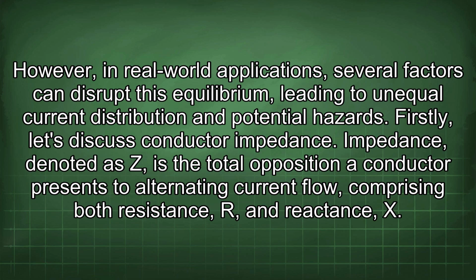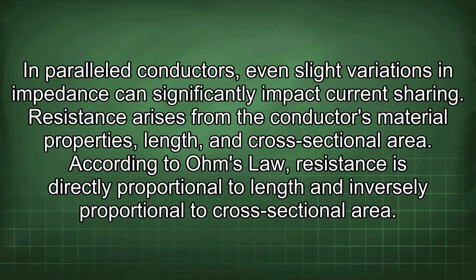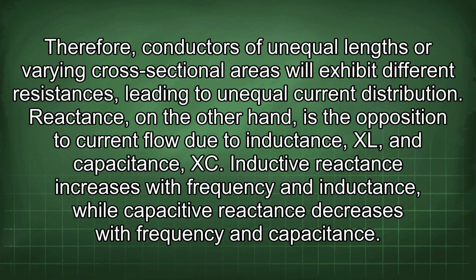Firstly, let's discuss conductor impedance. Impedance, denoted as Z, is the total opposition a conductor presents to alternating current flow, comprising both resistance R and reactance X. In parallel conductors, even slight variations in impedance can significantly impact current sharing. Resistance arises from the conductor's material properties, length, and cross-sectional area. According to Ohm's law, resistance is directly proportional to length and inversely proportional to cross-sectional area. Therefore, conductors of unequal lengths or varying cross-sectional areas will exhibit different resistances, leading to unequal current distribution.